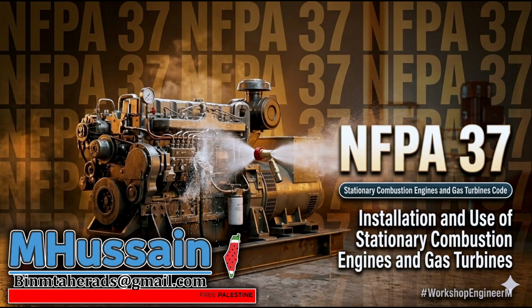Man, that's a stark division of labor. So at what point does this hazmat team actually step in? Like, what triggers NFPA 37? The entry point is 15 kilowatts. Anything rated above that triggers the standard. Wait, 15 kilowatts? What does that actually look like in the real world? It's pretty small. Like a 10 kilowatt portable generator you buy at a hardware store is exempt. Right, the kind you'd use on a job site.